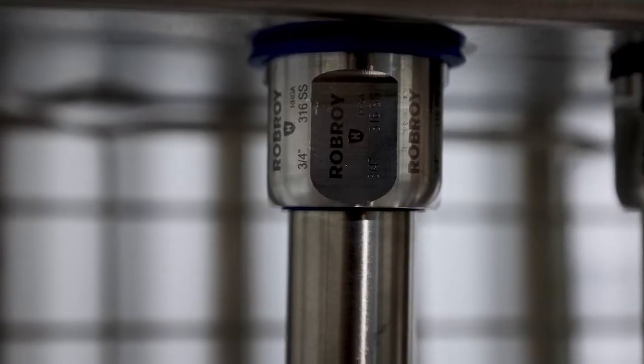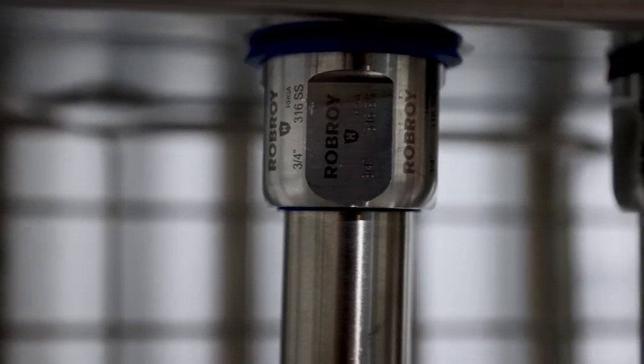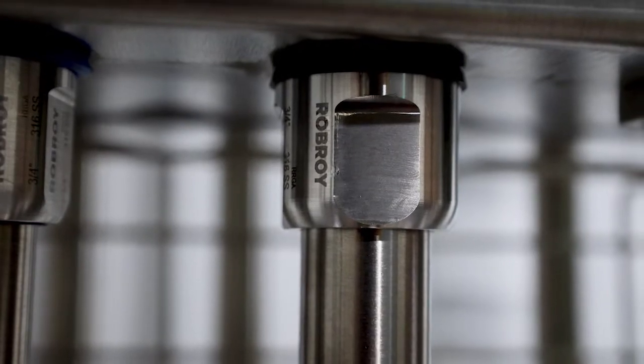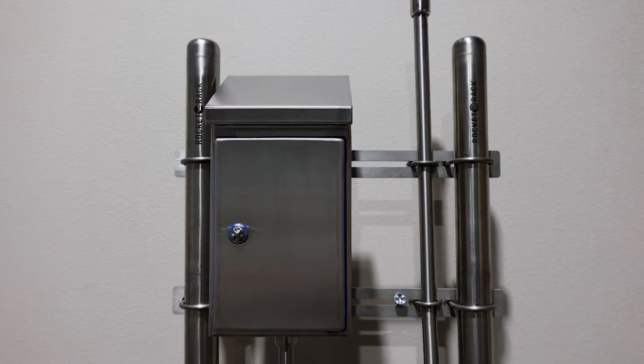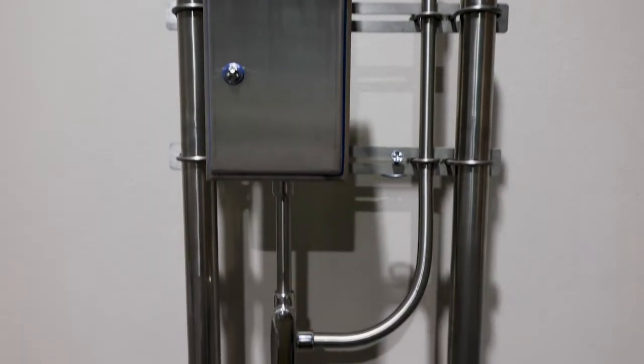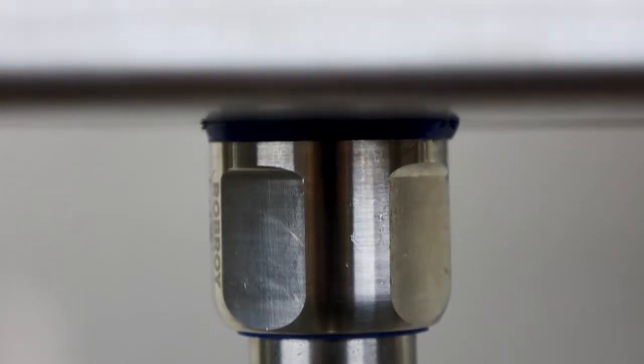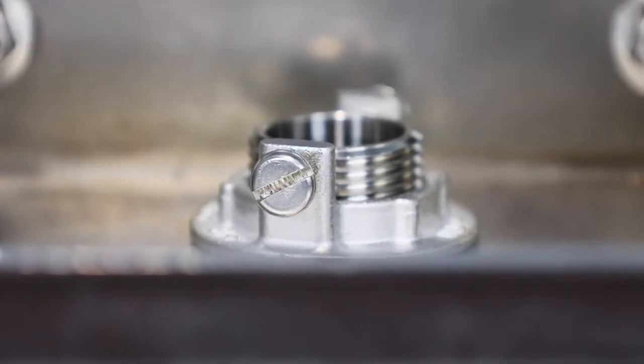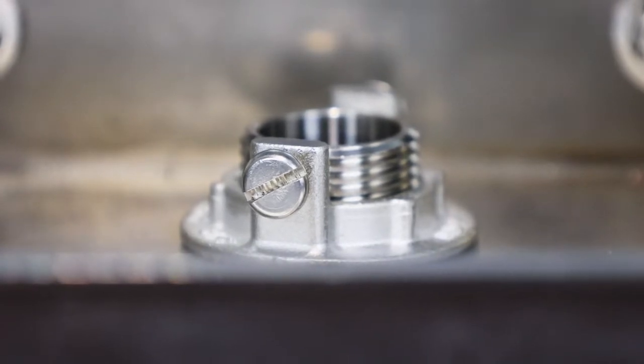That's why we recommend using Robroy Stainless Steel Conduit Hubs, along with the entire family of Robroy Stainless Steel products, to ensure a complete, uncompromised installation. Robroy Stainless Conduit Hubs are used to safely and securely terminate stainless steel rigid conduit to a box or enclosure. Conduit Hubs attach to boxes or enclosures by installing the male threads of the conduit hub body through the opening in the enclosure and securing with the lock nut provided with the hub from the inside of the enclosure.